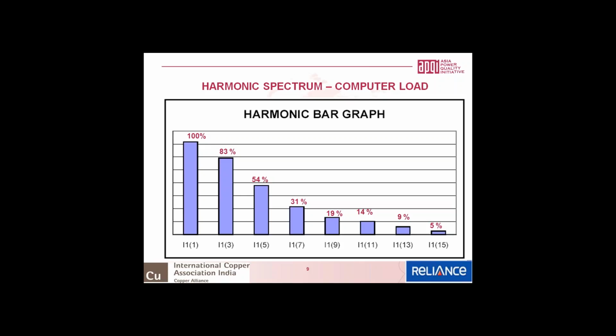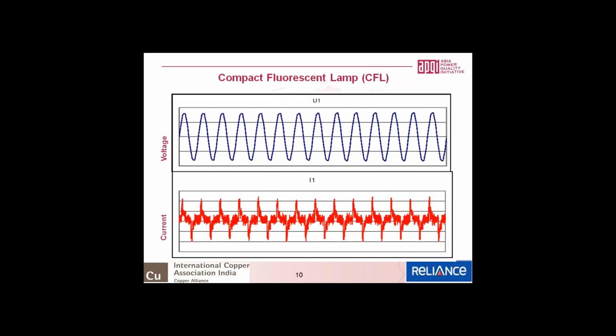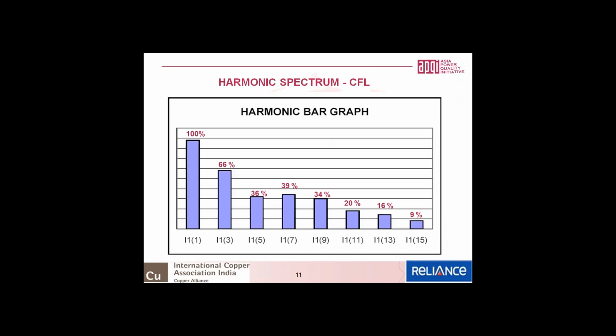Now let us talk of the compact fluorescent lamp. Between the voltage and the current, you can see that the current is completely distorted. If you extract the harmonic components, you can see that the third harmonic is extremely high, and the CFL is used very widely in residences now. You can see the amount of harmonics we are actually injecting into the system because of the CFL.